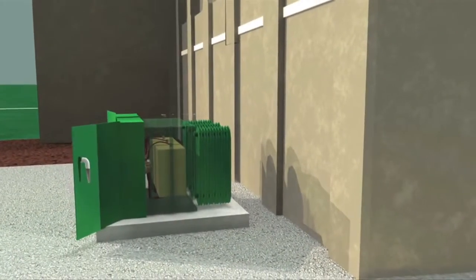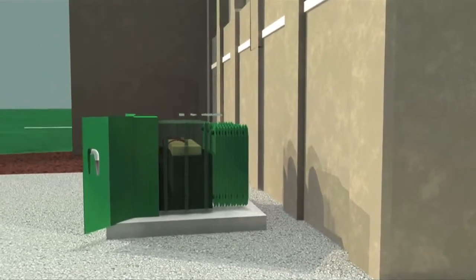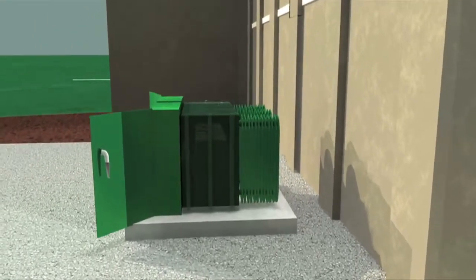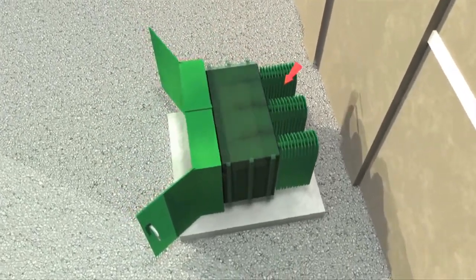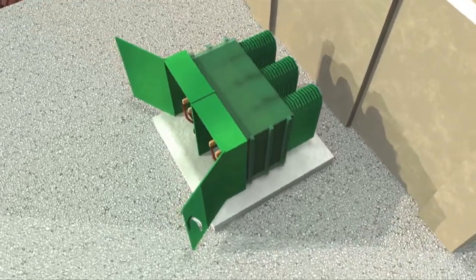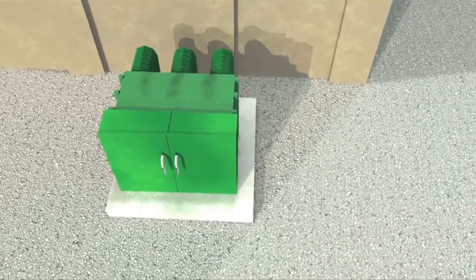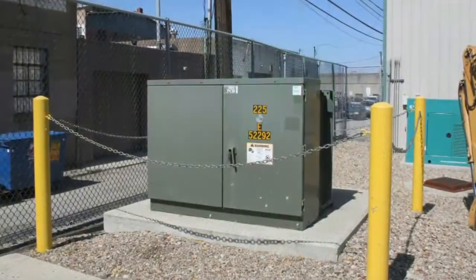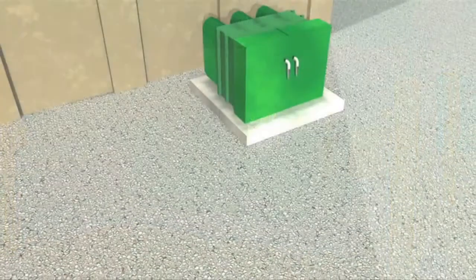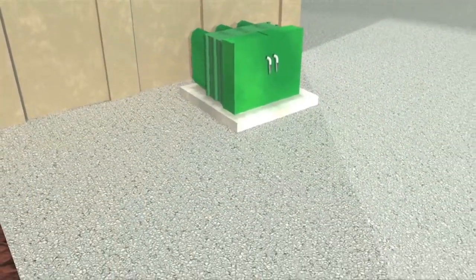The oil in an oil transformer is used for cooling. The core is filled with non-conductive oil. In most cases, mineral oil is used. Traveling through fins cools this oil, which utilizes the convection process. Usually, there are no pumps in smaller oil transformers. In addition to fins, some larger oil transformers will have exterior fans with thermostats that blow additional cool air over the fins. Oil transformers are placed on a concrete pad and almost always located outside the facility. This is in part due to a high fire risk.